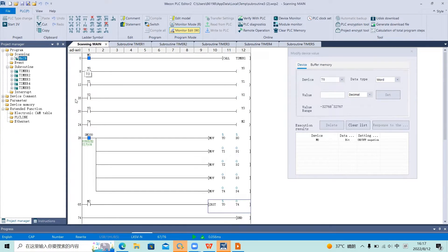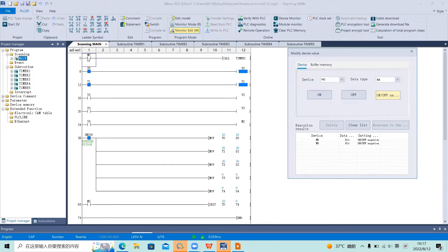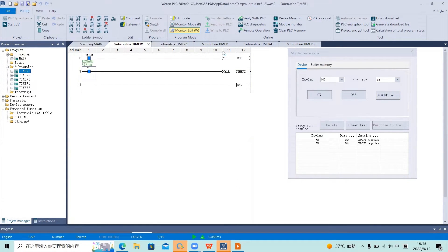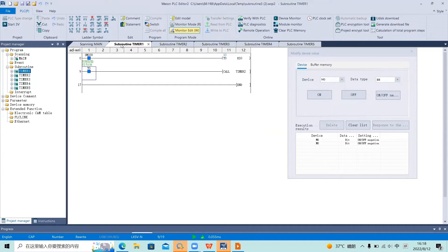When T4 is turned off, all the timers are cleared and they will turn on one by one again. When I turn off M0, the timers stop timing because we are no longer calling the subroutine. All the other subroutines will not be called either, because the first subroutine is not called, so none of the others are called.